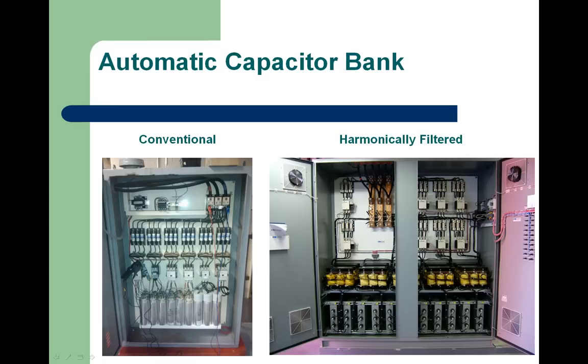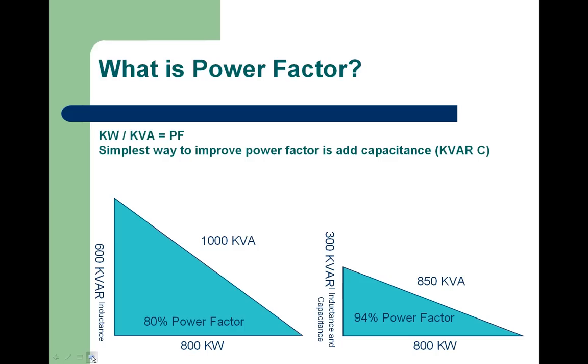But here we have a similar capacitor bank. We have our fuses for the individual steps. We have our contactors, and these small transformers are actually tuning reactors, and they limit the amount of harmonics that a capacitor bank will actually absorb if you have harmonics in your site. Now we're just going to get back here to, we're talking about kVARs, or inductive kVARs. This goes back to Pythagoras' theorem for the calculations here, but normally, in most cases, capacitors are installed at the main switchboard in a facility, typically today.